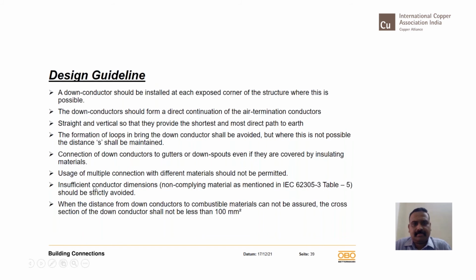Coming to the design guideline, a down conductor should be installed at each exposed corner of the structure wherever possible. Because the corners emit more charge, there can be chances of side flash from the trees, so the corners need to have a conductor to avoid side flashes. The down conductor should form a direct continuation from top to bottom. It should be straight and vertical so that it provides the shortest path in dissipating the current without any damage to the building or the circuits inside.